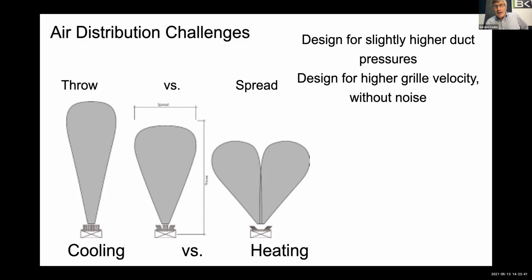So I would say design for slightly higher pressure in your duct system and design for higher grill velocity, of course, without creating noise. And you're going to say, what level is that? It's got to be less than 900 feet per minute. How do I know that? Because I've measured it. And more importantly, I'll say it this way. ASHRAE says not over 900. AHRI says not over 900. And every homeowner I've ever measured who tells me the grill is noisy, it's always over 900.